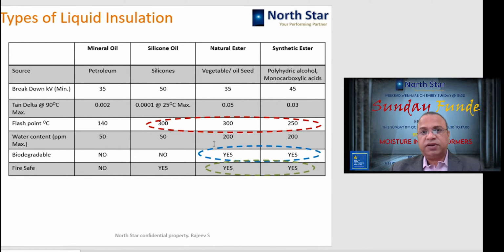Natural ester, if we look at it, as far as breakdown strength is concerned, is at par with mineral oil. Tan delta is slightly high compared to mineral oil, but the flash point is double that of mineral oil, it is 300 degrees centigrade, and the water absorption capacity is 200 ppm, almost 4 times that of mineral oil, and this is biodegradable and it is fire safe.